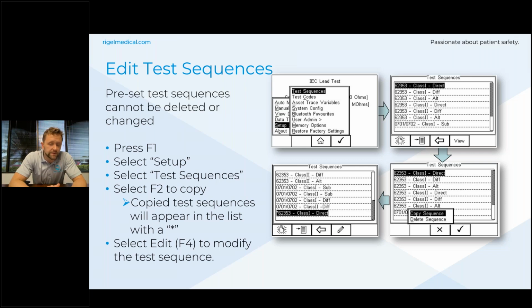But if you want to make any amendments, for instance, if you want to add in your own user tests, you want to add in a visual test, or you just want to change some of the limits, revisions of NFPA 99 are always changing. So there may be an instance where a facility is using an older version of NFPA 99. Then it's possible to go in there, change those limits so it's more specific to your facility, and then the test sequence is built in there for any of your future testing. So this is one of the ways you can go in there and edit those, and I'll show you how to do that on the 288 itself.